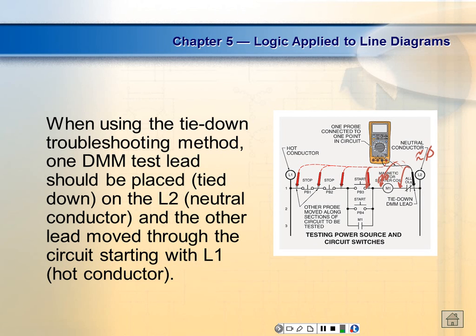But this is the way you troubleshoot. What you need to do is go to those manufacturer numbers, right? You understand? So we check it here, we check it here, we check it here, and we check it there. If you check it here and you don't have something, and you check it there and you have something, then it's a what? It's a wiring problem. And we have people where it doesn't pop into their mind. Well, I don't have voltage here, or I have voltage there, but it's connected right. Now, I hear that all the time in this class. It's connected right. It's connected right. But guess what? It wasn't.